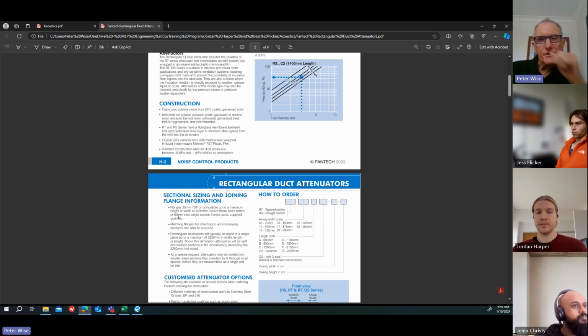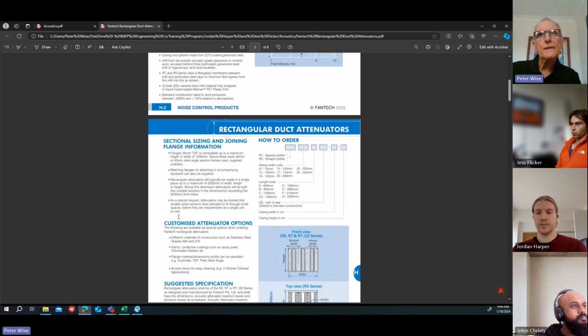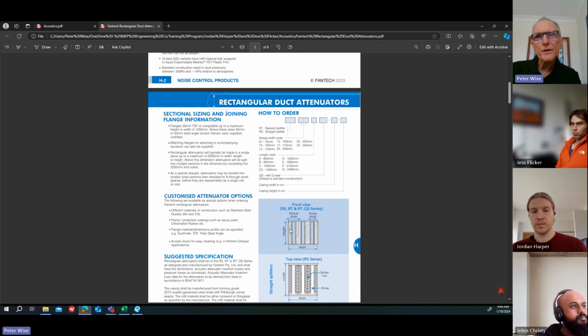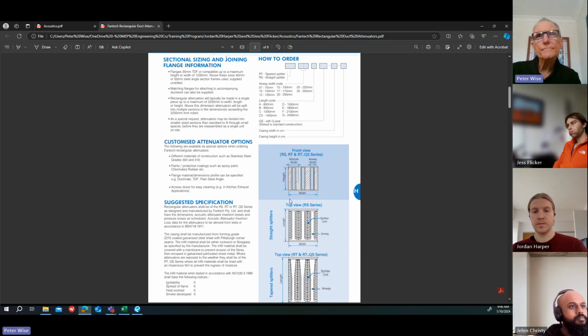So if you go through this, this is in their catalogue. You can go through and find out all the data, just to give you an idea of what the terminology of an attenuator is: RT, tapered splitter; RS, straight splitter. Now you have different numbers, which is the airway width code, which is, if you look at these diagrams, the width of the airway between the splitters. So that's those codes there, 07 up to 25. Then there's a length code, A, B, C, C2, etc., which is the length of the attenuator, which is shown on that diagram. And then there you can have Q-Seal, which is the Melinex lining.